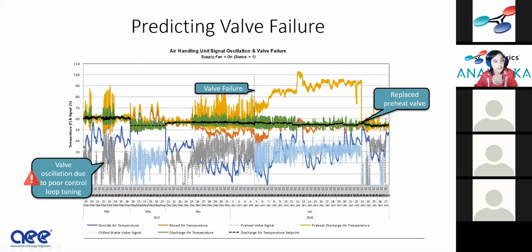Now, this valve was oscillating for a year before this valve failure. We have a metric we call rate of travel, but it essentially says this is how much this valve is oscillating in a minute or in a certain period of time, right? And anything over this number is going to lead to equipment degradation. We have 30 years of experience to know what that number is and what's bad. There's also rated cycles for equipment, but we can really fine tune this and be able to help the team loop tune. This is a situation where they might want to tune the loop.